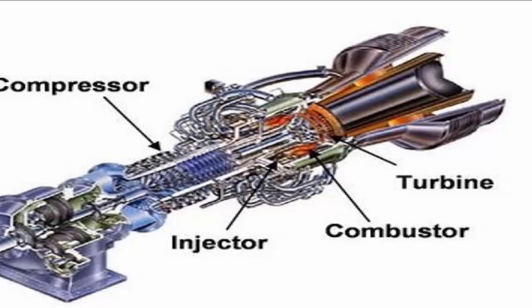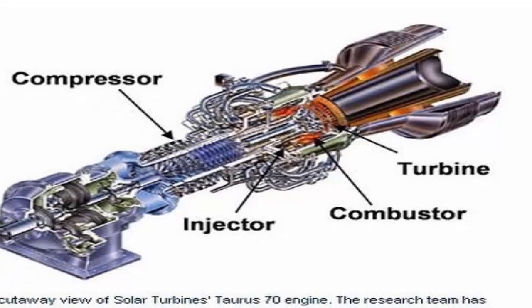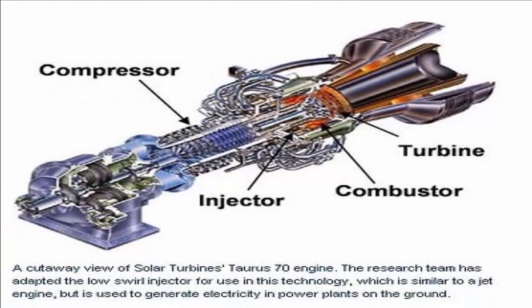Land-based gas turbines are of two types: heavy frame engines and aeroderivative engines. Heavy frame engines are characterized by lower pressure ratios, typically below 20, and tend to be physically large. Pressure ratio is the ratio of the compressor discharge pressure to the inlet air pressure.